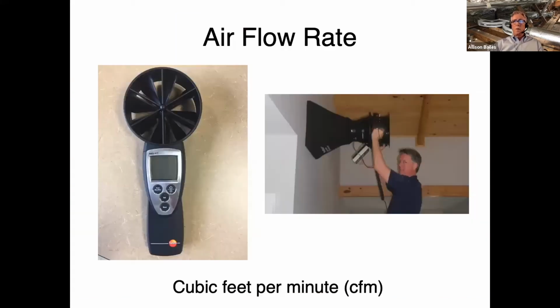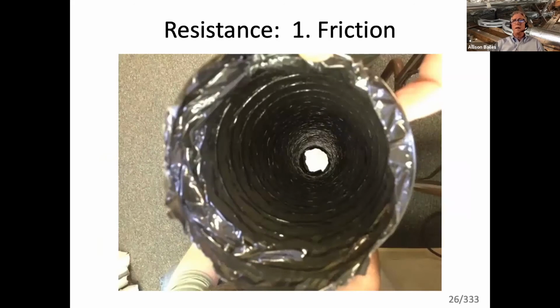And one of those is the airflow rate. The blower has a pressure rating, and for each pressure, there will be an airflow, and that airflow and the pressure go together. So the CFM and the static pressure go together. They're determined by the air handler. But you also put a duct system on there, unless it's a ductless unit. And there's a couple of things that affect your ability to move the air, the amount of air that you want to the places where you want it. One is the resistance of the air against the surface on the inside of the ductwork. And so you can put it through sheet metal, which is nice and smooth.